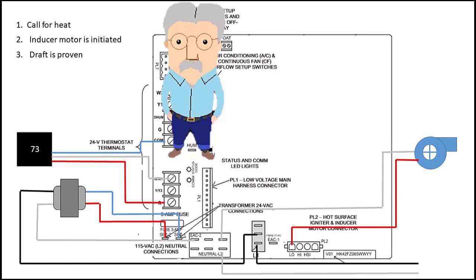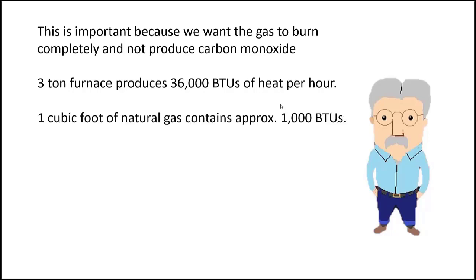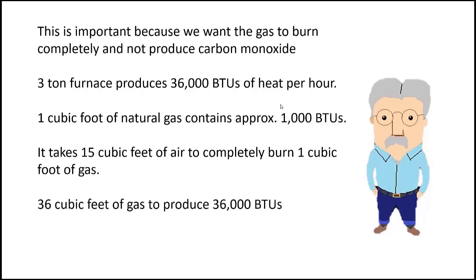The next step in the sequence is draft must be proven. Now this is very important because we don't want to produce carbon monoxide. And in order to do that, we need to provide enough air. A three ton furnace produces 36,000 BTUs of heat per hour. One cubic foot of natural gas contains approximately 1,000 BTUs. It takes 15 cubic feet of air to completely burn that one cubic foot of gas.